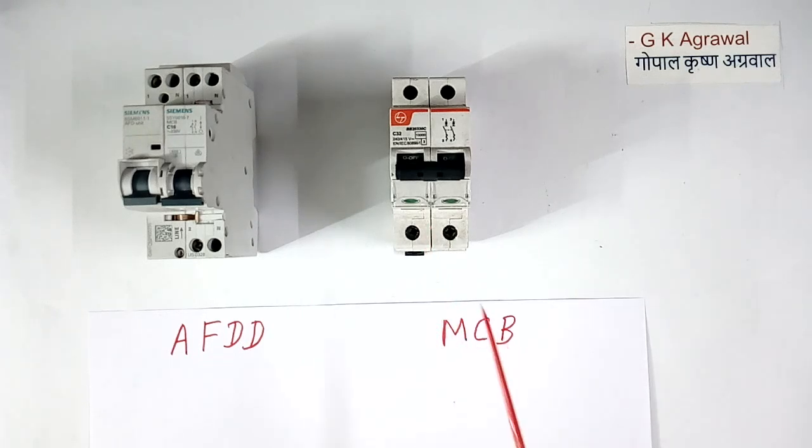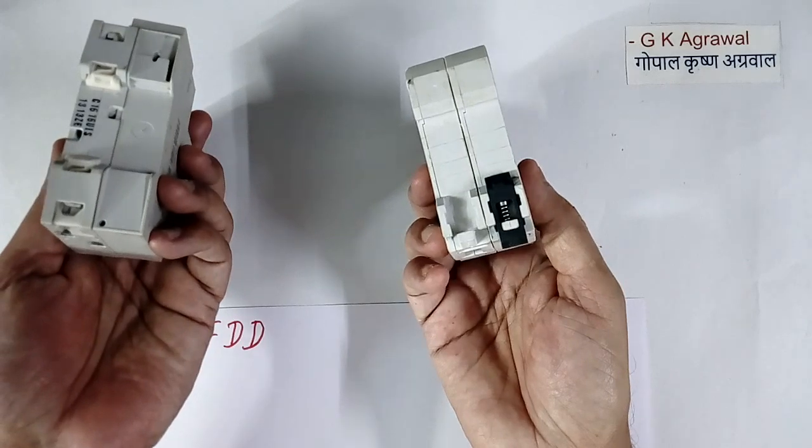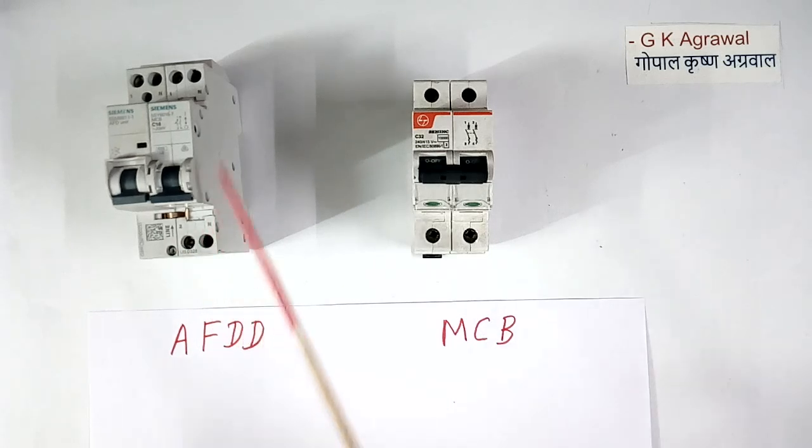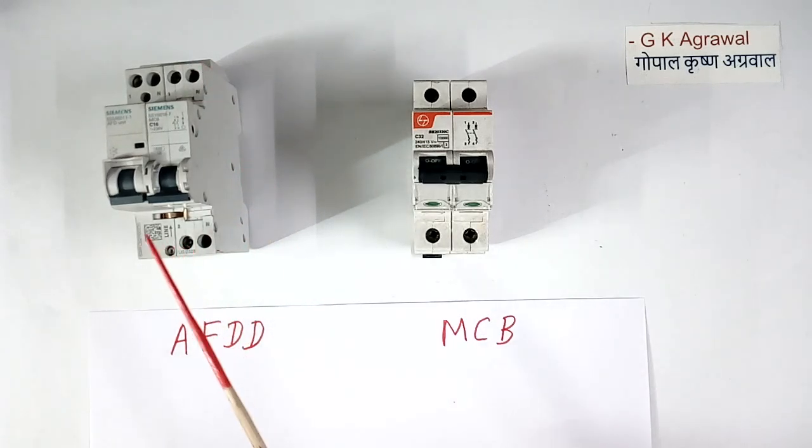This is normal MCB breaker of L&T make. This is AFDD breaker, what we are discussing now, of Siemens make. Both look similar. From back side, mounting arrangement is similar. So if you have this MCB, it is very easy to replace this MCB with this. This has one line and neutral supply, and this is load. No extra supply is required for electronic circuit. Everything is inside. Sometime arc takes lot of time to generate fire. In the mean time, this AFDD can trip the system and you can repair the system.